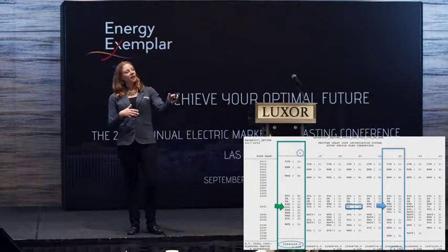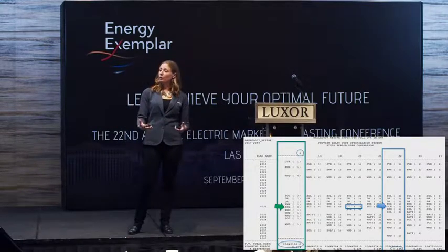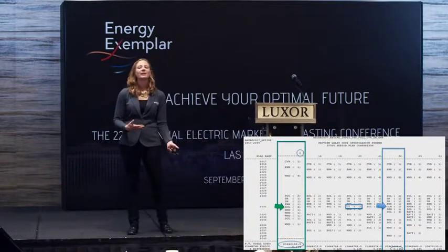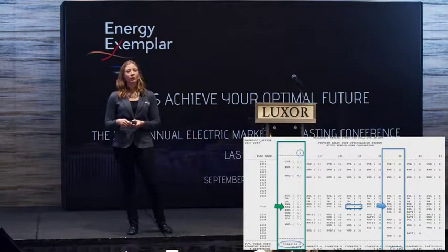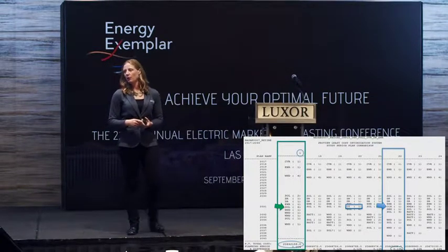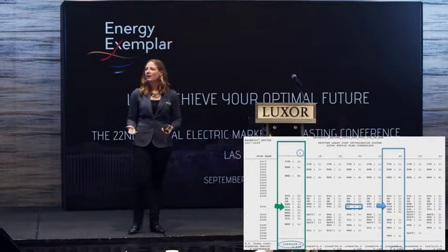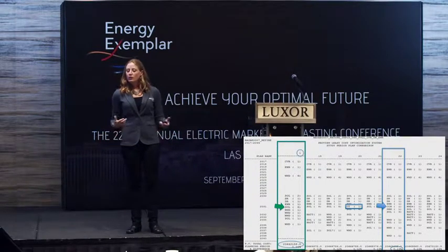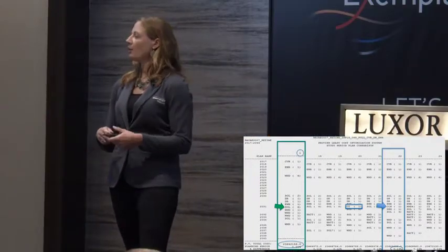Speaking to, so that kind of covered 1 and 4 of my evaluation factors. For this example, number 2 and 3, which was the types of resources selected and the timing. Well, for the timing, you can look at that solar. So that green arrow solar selection in 2031 represents 3,200 megawatts of solar that Strategist wants us to install in 1 year. Well, let's be honest, that's just not feasible. So we knew that wasn't feasible. Obviously, again, Strategist is just generating based off the numbers.